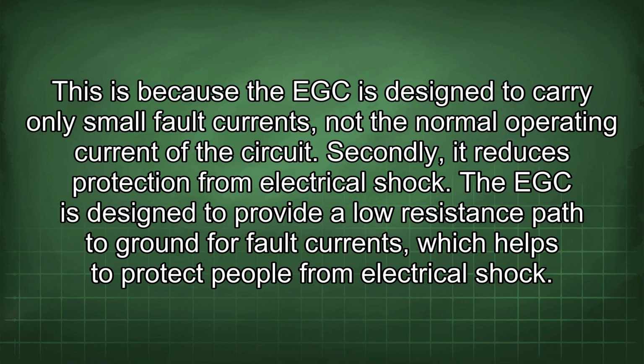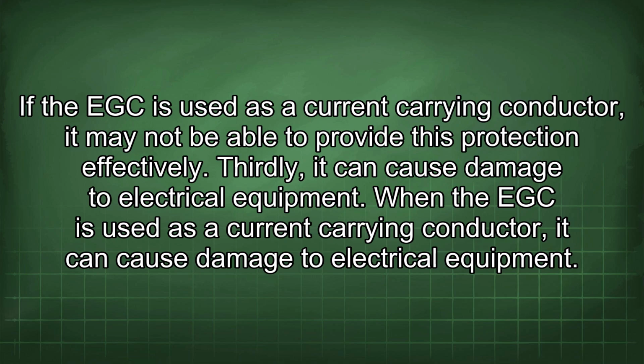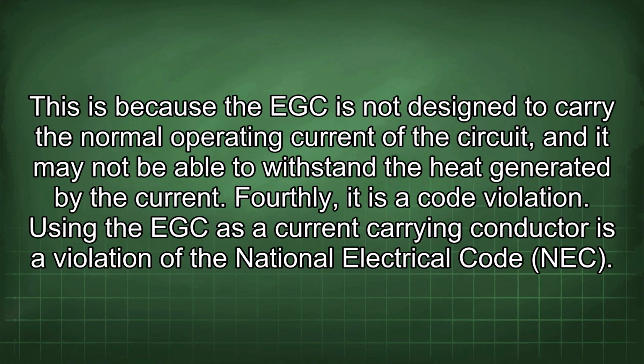The EGC is designed to provide a low resistance path to ground for fault currents, which helps to protect people from electrical shock. If the EGC is used as a current carrying conductor, it may not be able to provide this protection effectively. Thirdly, it can cause damage to electrical equipment. When the EGC is used as a current carrying conductor, it can cause damage to electrical equipment. This is because the EGC is not designed to carry the normal operating current of the circuit, and it may not be able to withstand the heat generated by the current.